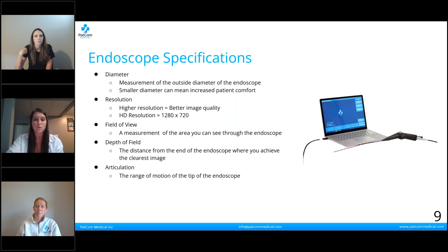Next is the resolution. So a higher resolution is just going to have a better image quality. Our distal chip scope does have a true high def resolution of 1280 by 720. Next is the field of view, which is the measurement of the area you can see through an endoscope. A wider field of view helps you see more of the pharynx and the laryngeal structures at once. This is very useful, especially when you're tracking bolus flow or airway protection. Next up, we have depth of field, which is just the distance from the end of the endoscope where you achieve the clearest image. And then the articulation. This is the range of motion of the tip of the endoscope. And this really does make a difference with just how you are passing through the nasal passage and just the range of motion that you have when you're in the pharynx.